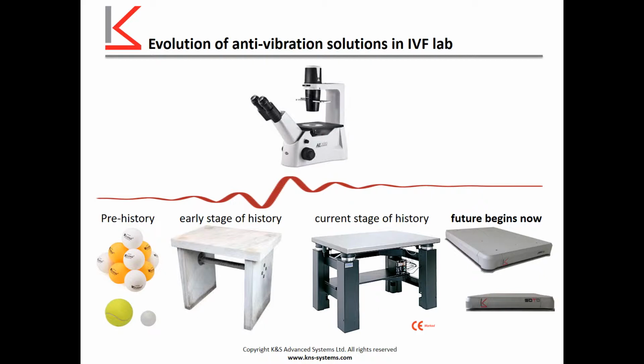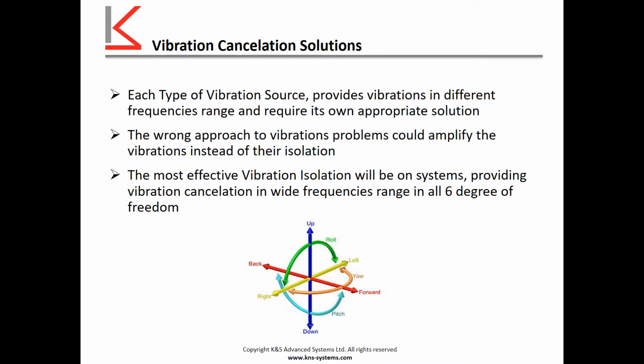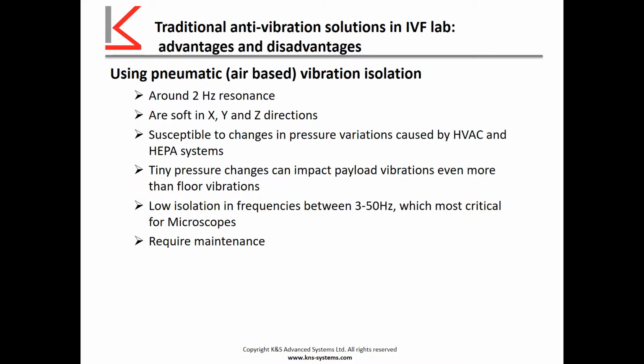If we take a look in the near future, which is starting just now and here, then we will see that KNS anti-vibration platforms are the most advanced and effective solutions for this purpose. Each type of vibration source provides vibrations in different frequencies range and requires its own appropriate solution. The wrong approach to vibration problems could amplify the vibrations instead of their isolation. The most effective vibration isolation will be a system which provides vibration cancellation in wide frequencies range in all 6 degrees of freedom. Most of the solutions used until now in IVF labs could resolve the problem just partially. However, not for all cases, and in some of the cases it even increased the problem.